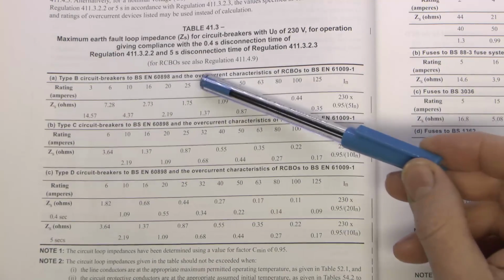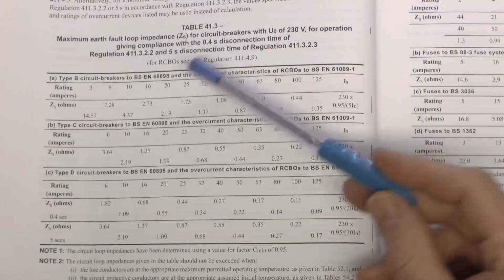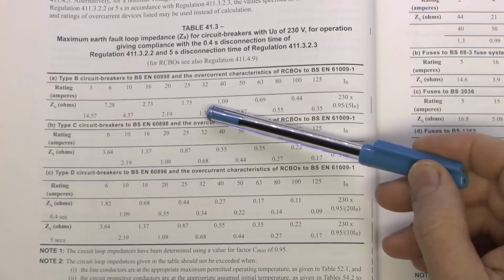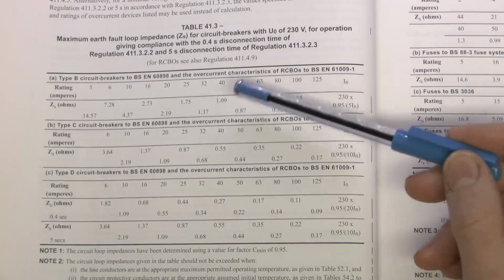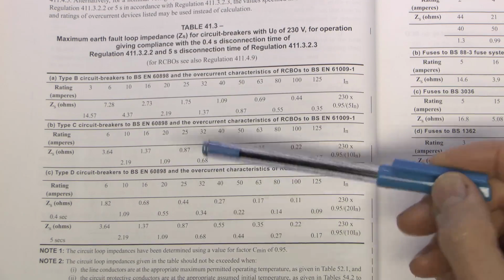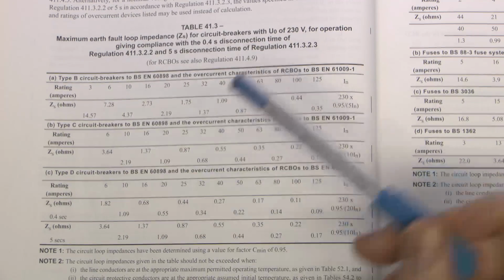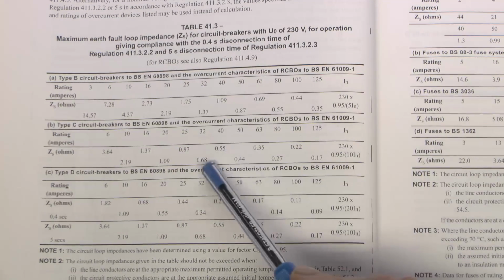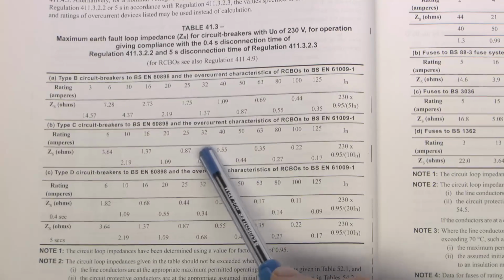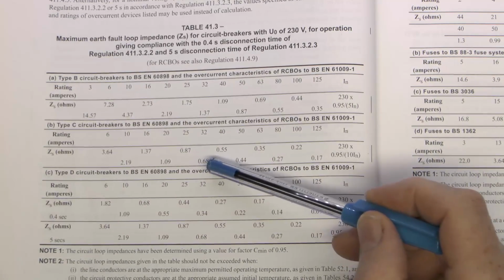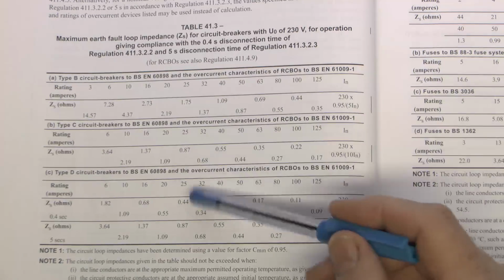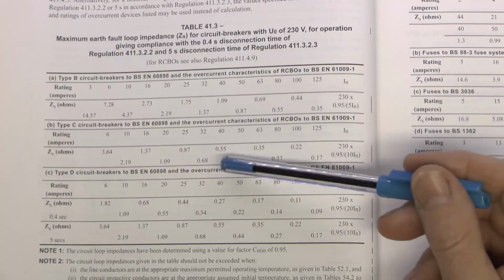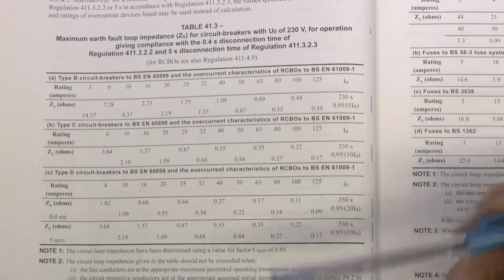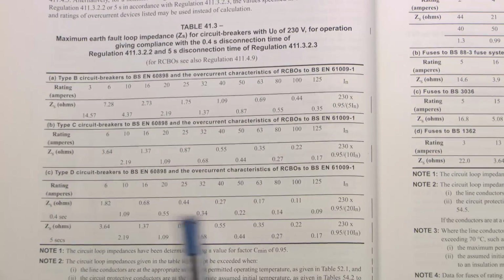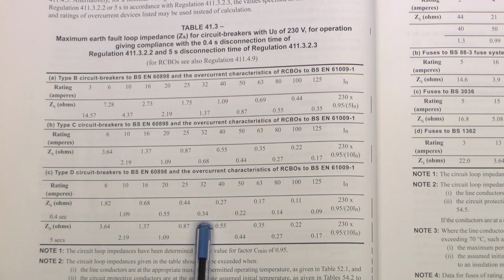But say have a look at the column here for 32 amp circuit breakers. Even on a type B, the maximum impedance is only 1.37 ohms. And then, of course, once you get into type C, you're needing a maximum impedance of 0.68. And bearing in mind, if you've got a certain type of supply, the external impedance could be a large proportion of this. So either you're going to have a very short circuit, as in not very long, or you're not going to be able to fit a type C. And of course, once you move into the type D, it's even worse. So for a 32 amp type D, maximum impedance of 0.34 ohms, so that's the circuit and whatever's outside.